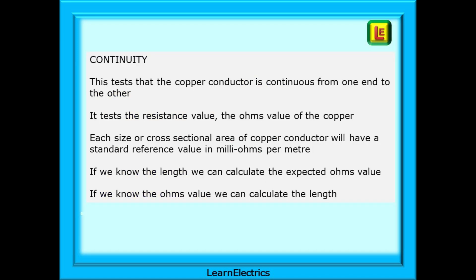When continuity testing we are testing that the copper conductor is continuous from one end to the other. It tests the resistance value, the ohms value of the copper. Each size or cross sectional area of copper conductor will have a standard reference value in milliohms per meter. If we know the length we can calculate the expected ohms value and make a comparison, and if we know the ohms value we can calculate the length.